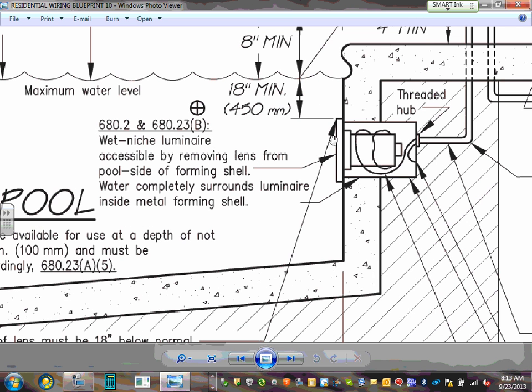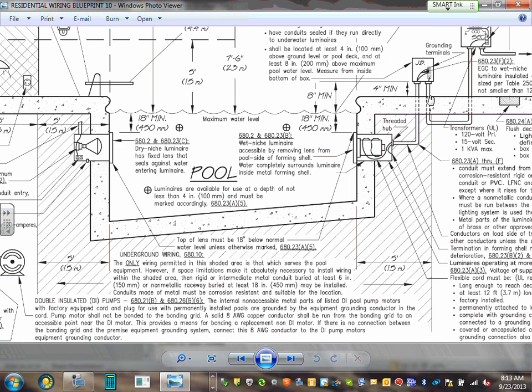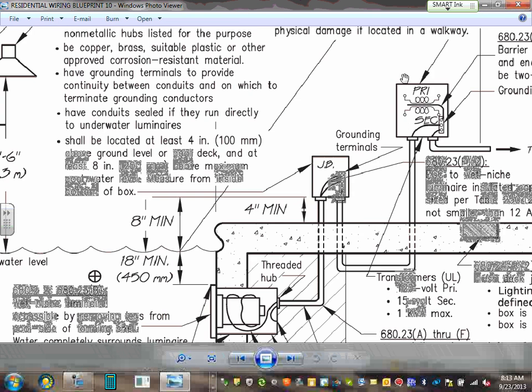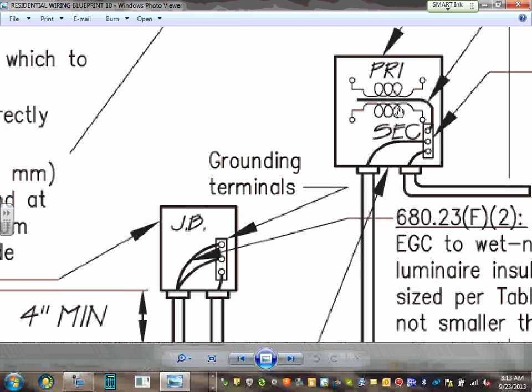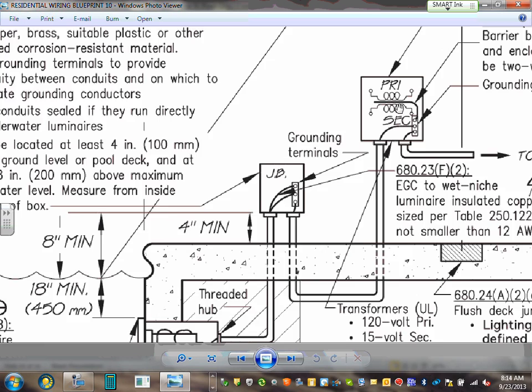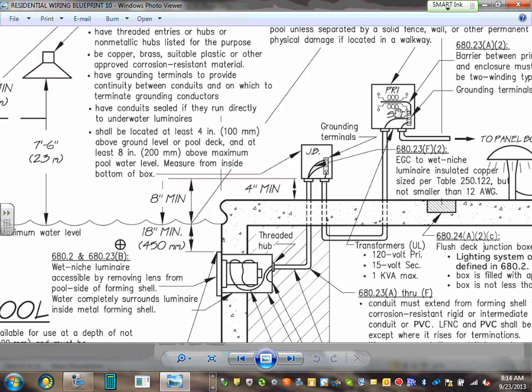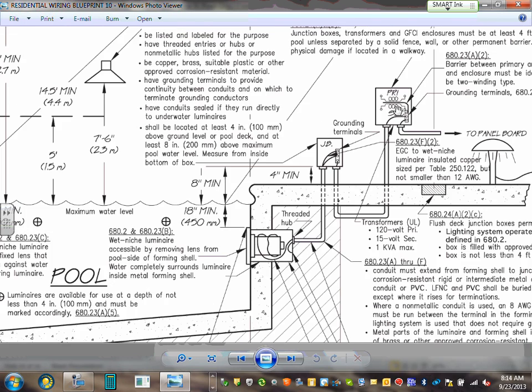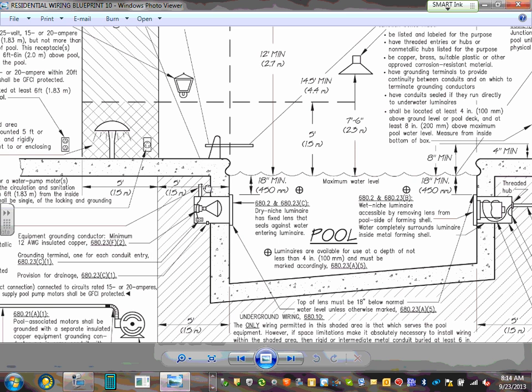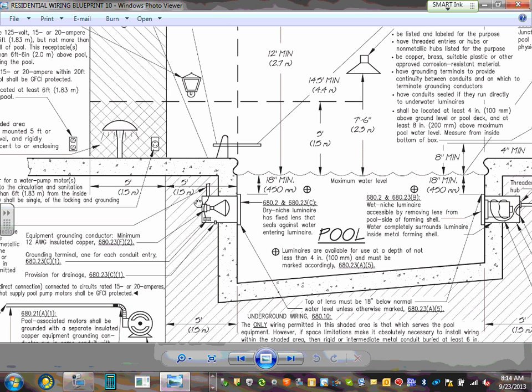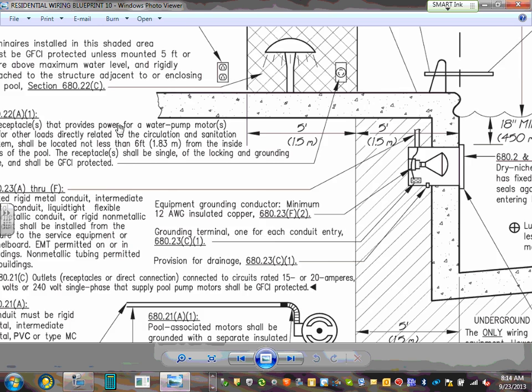Wet niche luminaire, the water can get in. That's okay. It's rated to have the water in it. Access by removing the lens from the pool. So you remove it here and change it. But look, all of them are coming from where? Can you guys see that? What is this? Transformer. It takes the high voltage to a lower voltage, isolates it, and feeds it from a GFCI. Well, if they're low voltage, you don't have to have a GFCI. And so for safety, can you guys see how they do that? They put a transformer, with an equipment ground conductor.